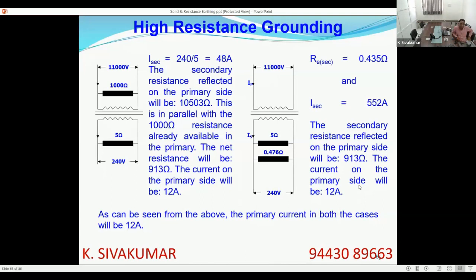In the right hand slide, to achieve the same result, I am not connecting an 11 kV rated 1000 ohm resistor on the HT side. I am connecting a 240 volt rated 0.476 ohm resistor on the LV side. Now, if you do your calculation, the effective resistance on the secondary side, that is parallel resistance R1 R2 by R1 plus R2 of 5 ohms and 0.476 ohms, is 0.435 ohms, the secondary effective resistance. If you multiply this 0.435 ohms by the turns ratio square, 11,000 volt by 240 volt squared, you will get 913 ohms in the primary. When you get 913 ohms in the primary, the current is 12 ampere. You see, in both the cases, the primary current is 12 ampere.